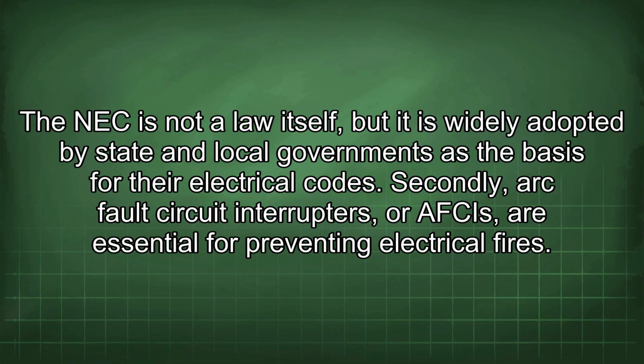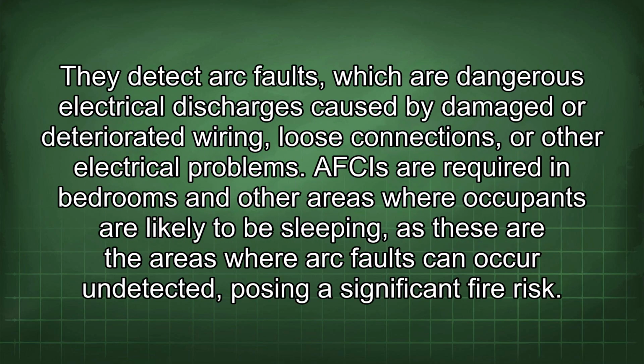Secondly, arc fault circuit interrupters, or AFCIs, are essential for preventing electrical fires. They detect arc faults, which are dangerous electrical discharges caused by damaged or deteriorated wiring, loose connections, or other electrical problems. AFCIs are required in bedrooms and other areas where occupants are likely to be sleeping, as these are the areas where arc faults can occur undetected, posing a significant fire risk.